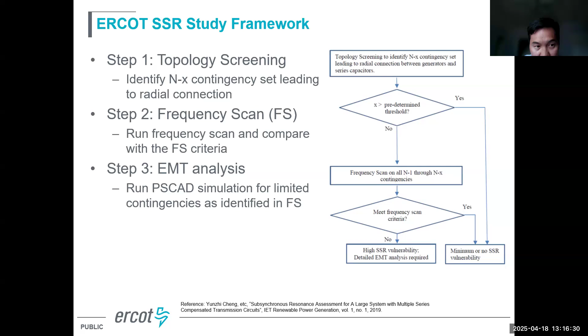So we first try to find out how many outages or contingencies cause the radial connection. And if that number X is very big, then we will conclude no SSR risk. Otherwise, we go to the second step, which is frequency scan. We run the frequency scan and compare with the frequency scan criteria. If it meets the criteria, then we conclude there are no SSR issues, and that's it. Otherwise, we go to the third step, which is the detailed PSCAD simulation to identify the real SSR or SSCI risk. So I'll talk about it a little bit step by step.